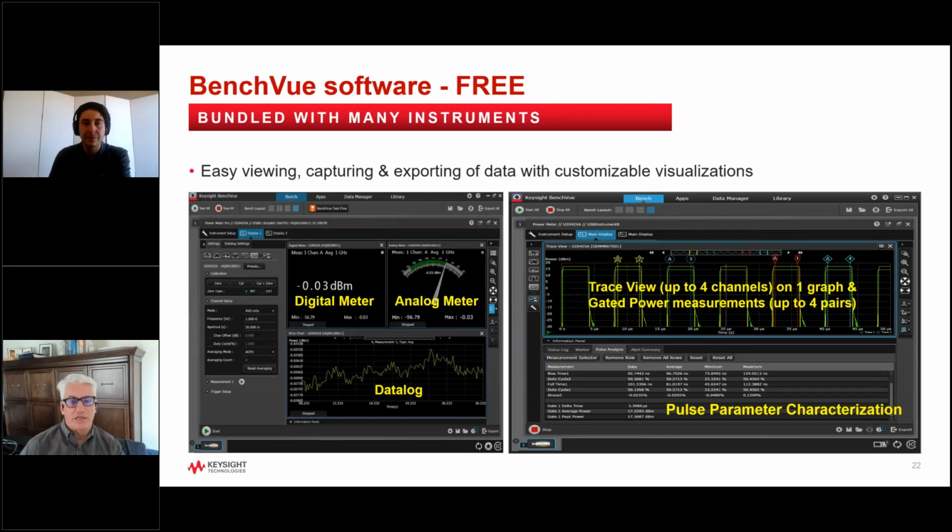If you go onto Keysight's website and search for BenchVue included, you can get more information on that process. But essentially, if you have one of them, you plug it in, it'll enable you to download that and license it. So pretty simple, and it's included with the USB and the LAN power sensors. What's more, connecting up any power sensor, BenchVue will recognize the specific model, serial number, and details of your meter. It's just as easy as plugging in.